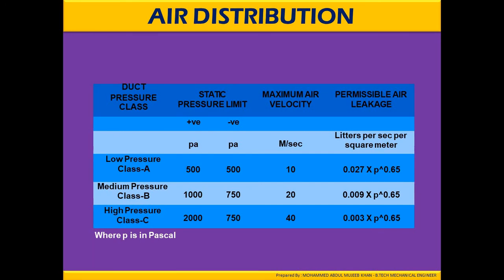These are the different classes of ducts and their static pressure limits, maximum air velocities, and permissible air leakages. Any duct in an HVAC system is classified into low pressure class A, medium pressure class B, and high pressure class C. Depending on the class and application, different pressure limits are obtained per SMACNA and ASHRAE standards, which define the maximum pressure drop and maximum air velocity.